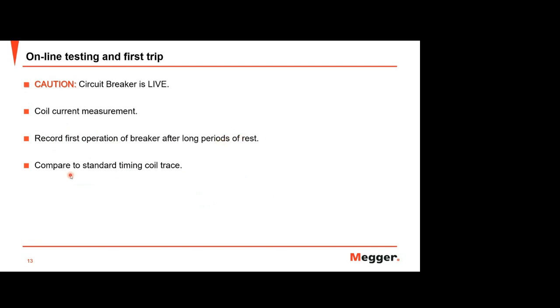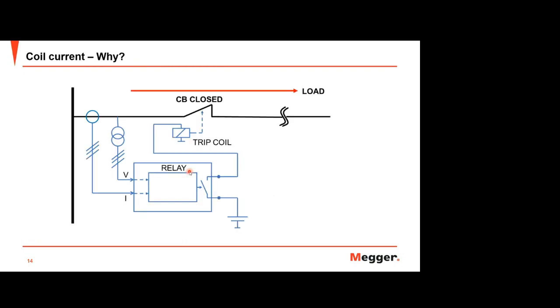And then you compare the standard timing coil trace with the reference result, or with the commissioning data reference. Now the question is why coil current? Why do we use just coil current to analyze the overall breaker? Yeah, the main reason, before I go there, this is just an illustration of how the breaker operates.